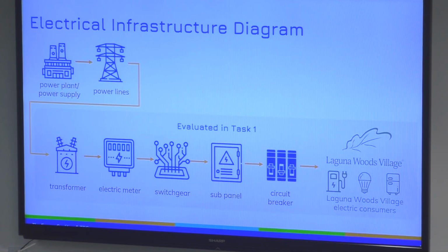Next we have the electric meter, which measures electric energy consumed. Then we have the switchgear. The electrical switchgear is made up of various pieces of electrical equipment used to distribute power to individual electrical loads, such as AC units or other outlets, electric ovens, etc. This provides protection during electrical incidents, like overloads or equipment failure. Switchgear is a general term comprising a single electrical panel or assembly of panels with switches, fuses, instruments, and other equipment mounted to serve the electrical load. Overloads can cause outages on the switchgear.